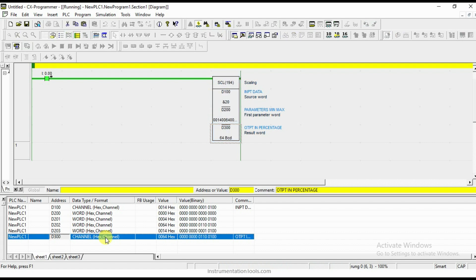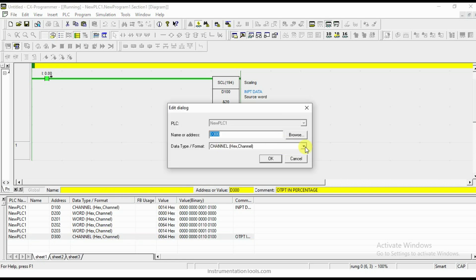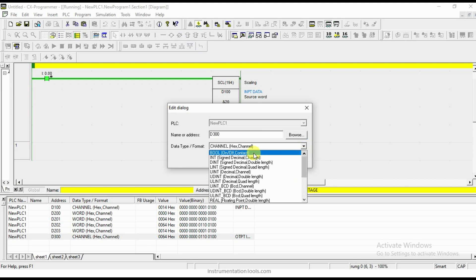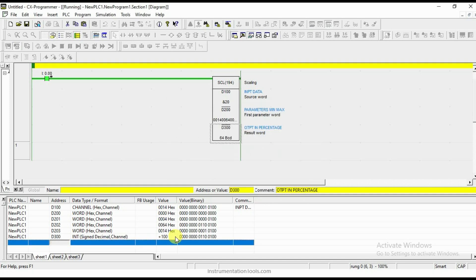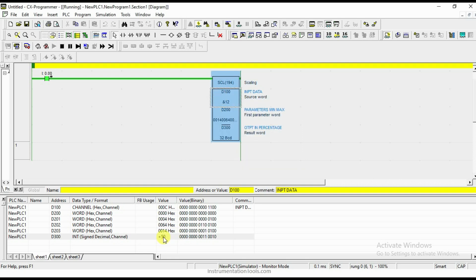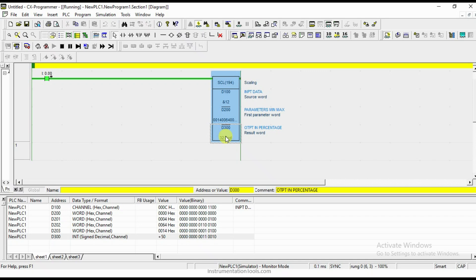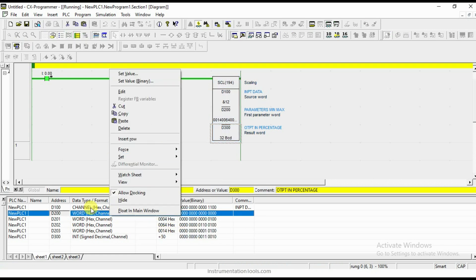I am trying to change the data type so you can understand better. Now you can see 100. I will give 12 — it should give 50, and we can see it is giving 50. The display was in BCD, which is why 32 appeared earlier — 32 BCD is nothing but 50 in decimal. Here you can convert so that you can see everything in integer format.